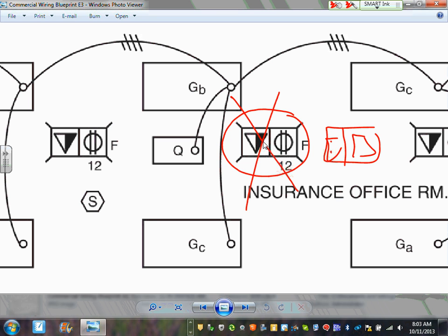So when you start laying out our power, when it comes to the cubicle and the open office, the option that we're asking for, I think it's the best option to wire it. There are other options. What are the other options? Here, you're looking at what they call power poles. But do you see how ugly it is, guys, how they're coming down? It's not good. That would be a great idea if we came from the bottom, so you don't have to see all these poles standing in the office.